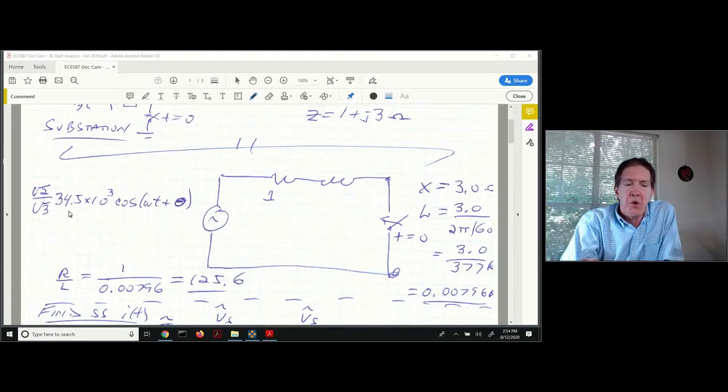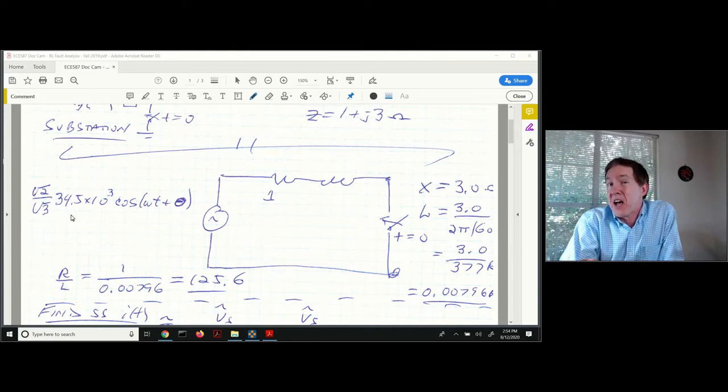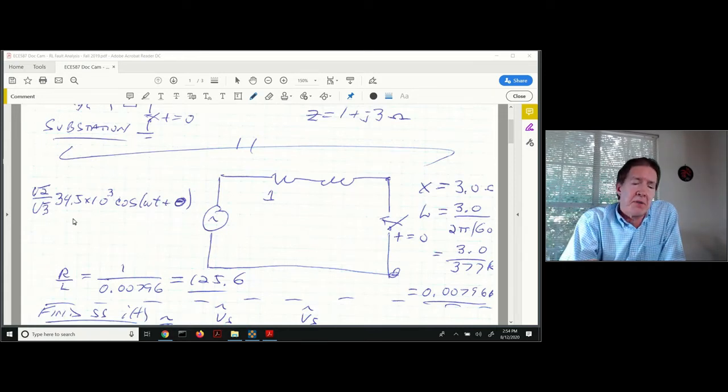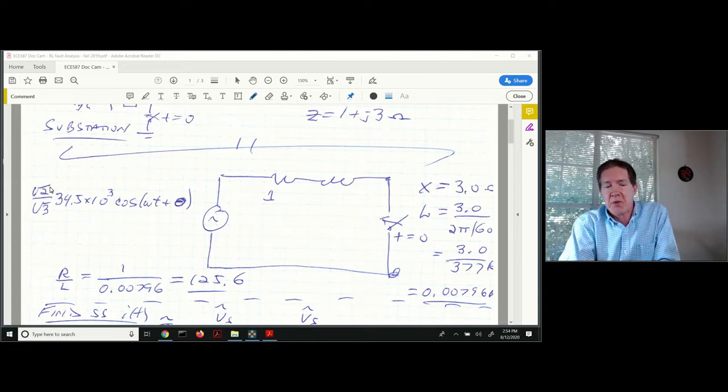If I've got 34.5 kV, that is a line-to-line value. Since this is a line-to-neutral type circuit, you divide that by square root of 3 to get the line-to-neutral value. Since this is an RMS value, you need to multiply by square root of 2 to get the zero-to-peak.